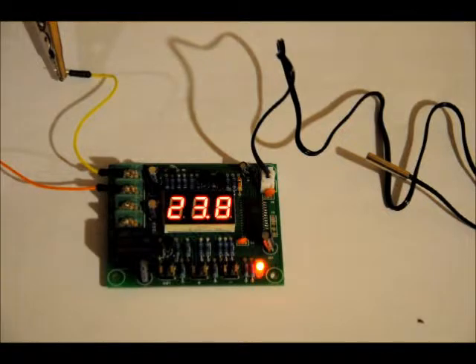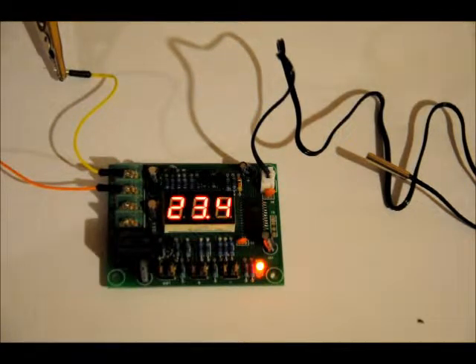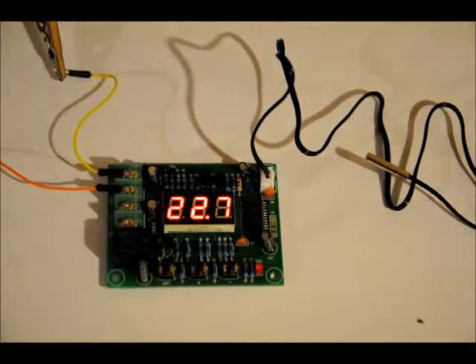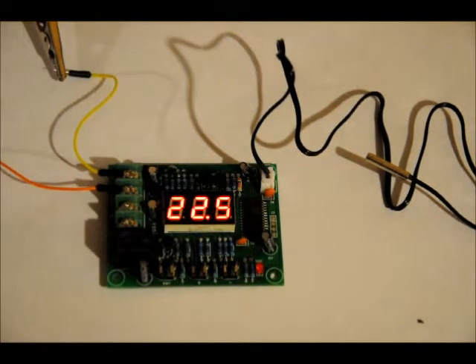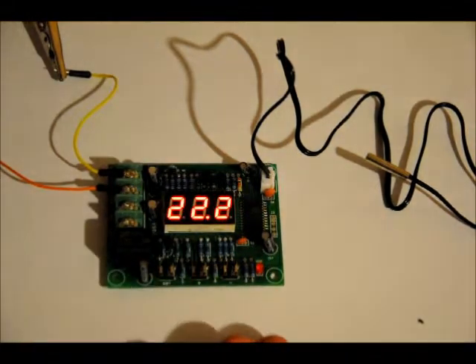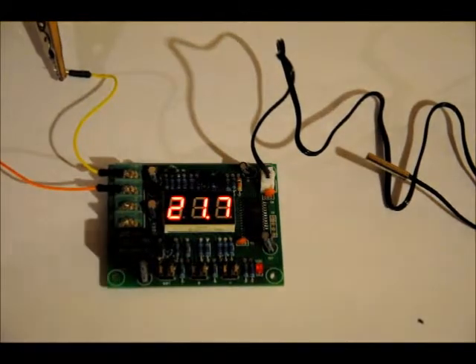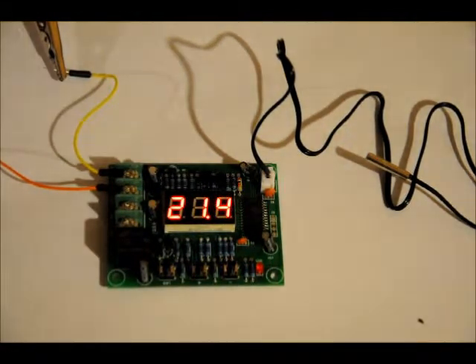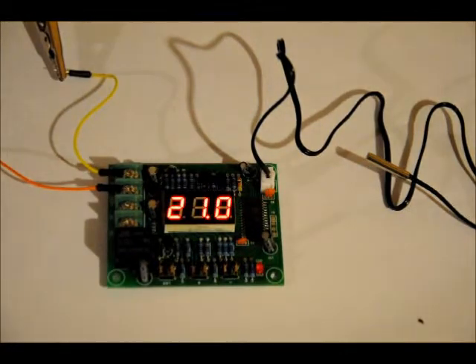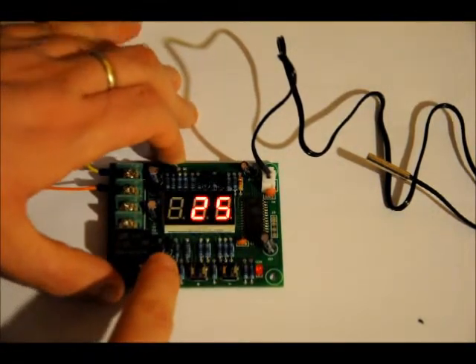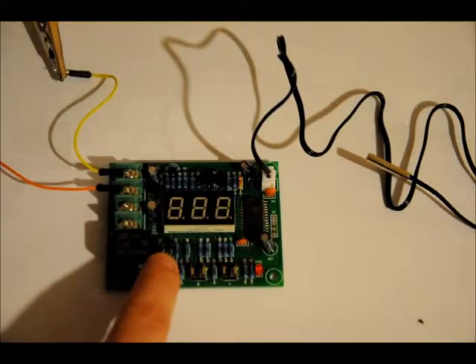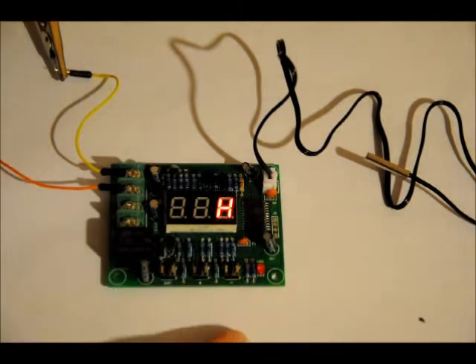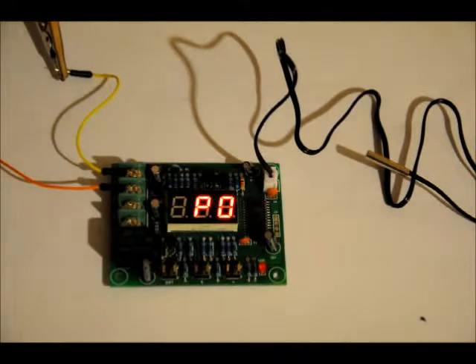Now alternately, if I change it to heating mode, which I will do in a second. If I change it to heating mode, and I set the normal temperature, or the reference temperature to 25 degrees, having a hysteresis value of two, the relay will turn on when the room temperature is below 25 degrees, and it will turn off when you bring it up past 27 degrees. So let's actually do that. I'll press the leftmost button again. Our reference temperature that we can change is to 25 degrees. P0. I'll press the leftmost button again. Cooling mode. Heating mode. Leftmost button. We'll just wait to go back to the current temperature.